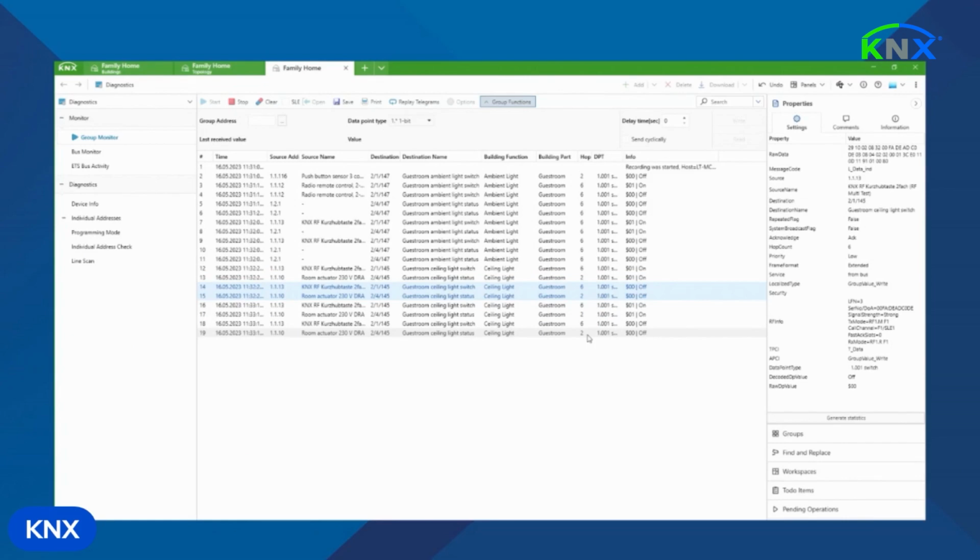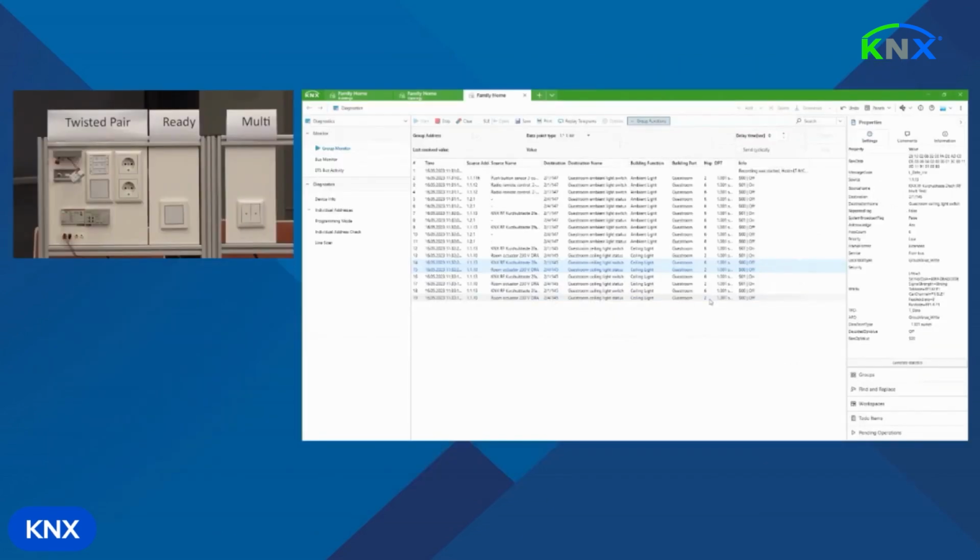You have this ready device, the remote control. Yes. And this is also linked to the switch group address, so to the control address. Therefore, the device sends the control message via ready. So that is also received by other ready devices which are linked. But the status is only sent back to this device which has a status LED. Your remote control doesn't, so it's not linked to the status address. So the status address is only linked to multi-devices. So ETS automatically configured this.